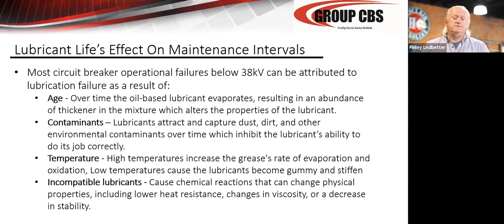Contaminants are a big deal: dust, dirt, all sorts of things, spider webs, corrosive materials. If you're close to the ocean, salt water, basically chlorides are the death of stainless steel. People think stainless steel is immune, it's not. You get a chloride close to it, it'll punch right through it in a matter of time. So make sure these are closed, they're clean, vacuum interrupters are clean, all the stainless is clean. Make sure there are no chloride-based cleansers used, no citrus-type cleaners used in cleaning your switchgear or your circuit breakers.